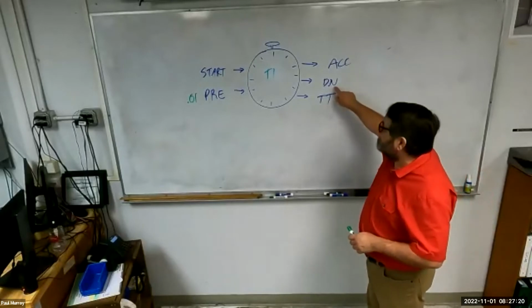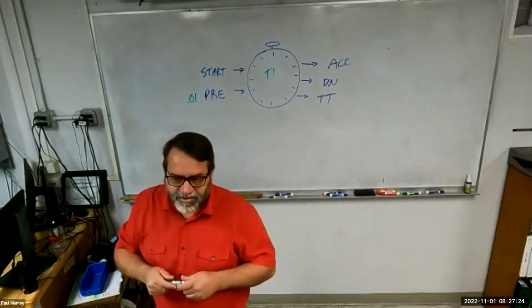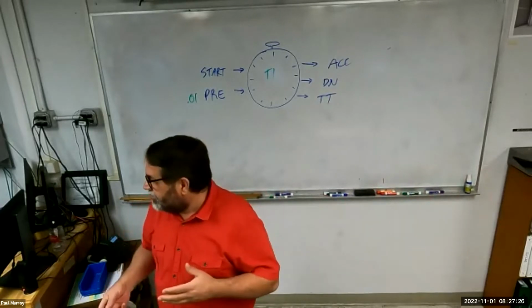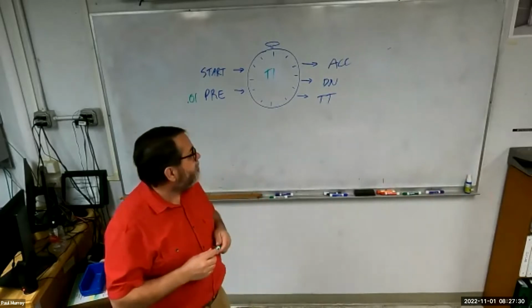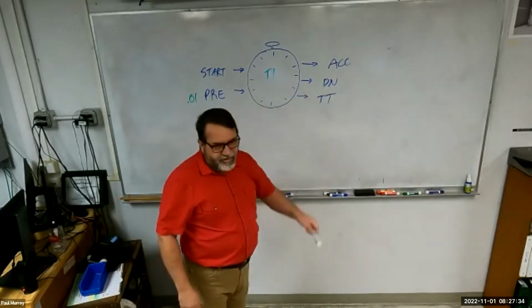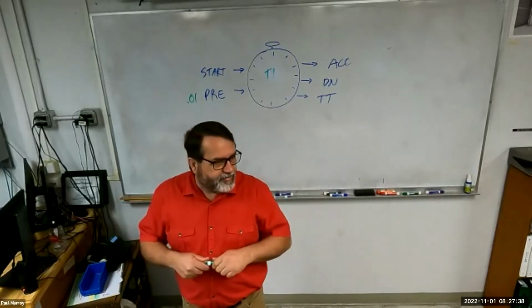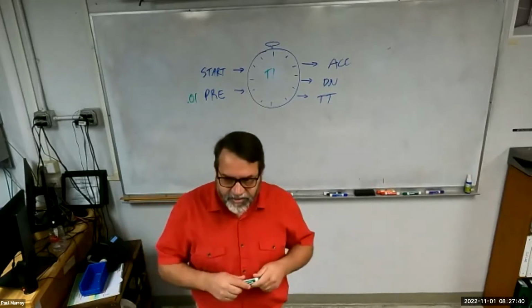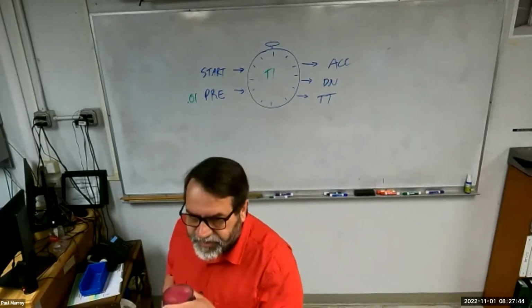So my done bit gives me a one-shot signal. Instead of worrying about a whole different command to learn how to use it, if I just want an instant signal, I just put in a really short timer and I use the done bit to get the signal out of it. Does that sound like a good idea?